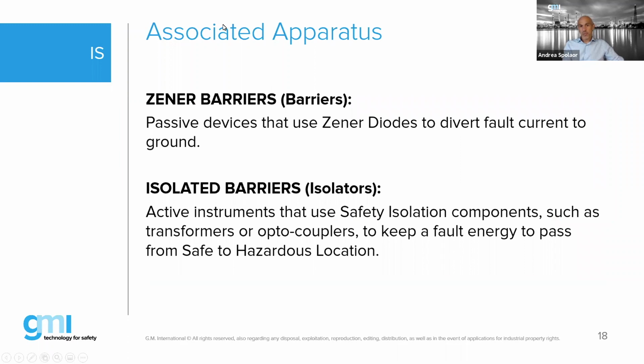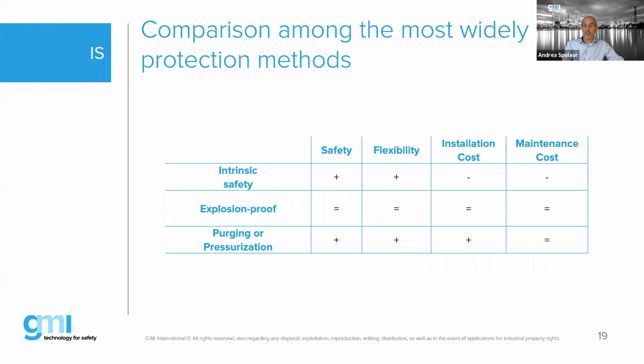So the associated apparatus unit can be Zener barriers. The first products used in the market are passive devices that use Zener diodes to divert fault current to ground, or isolators. Isolators are active instruments, and within the unit there is a transformer and/or optocouplers that keep out from the hazardous area any energy that can cause an explosion. So that is the difference between Zener barriers and isolators.